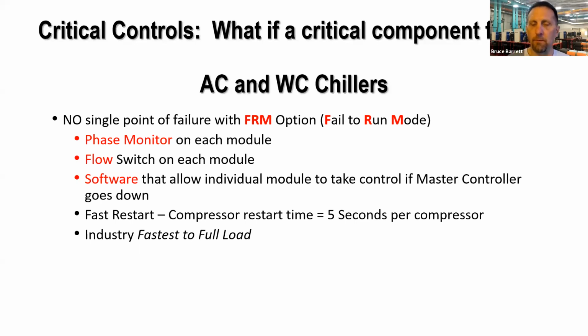Scroll compressors offer a very fast restart opportunity. So it's simply as fast as we can go is 5 seconds per compressor. So if I have 10 compressors, I can be at full load in 50 seconds. Very fast, back to full load.